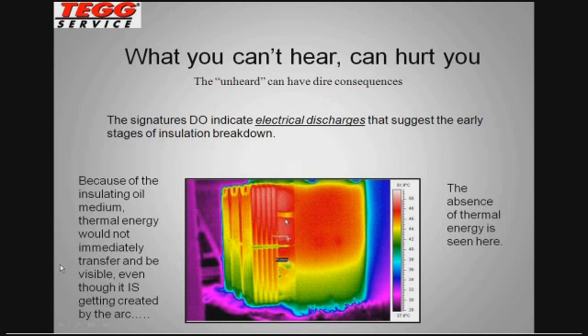The slide I have up currently shows what a liquid-filled transformer should look like to the infrared camera, meaning we have a very uniform and consistent pattern all the way across the area of the vessel. When infrared sees an issue like this, particularly on a liquid-filled transformer, it's typically too late. So to answer the question most specifically, the ultraprobe in many cases can provide earlier indication of problems within components that you cannot get a line of sight to than the infrared camera will. If you do see it with the infrared camera, it's probably in the latter stages of failure, and you may not be able to act soon enough.